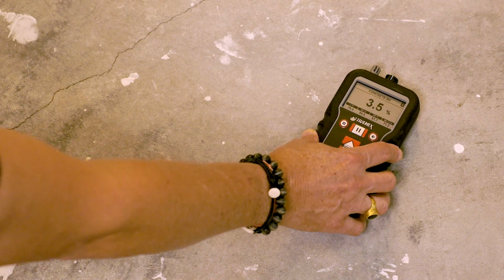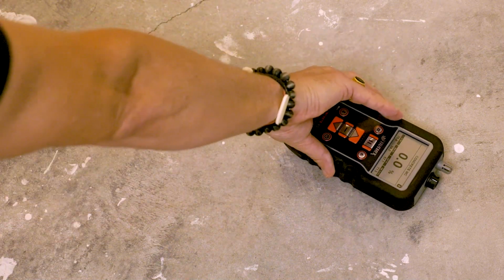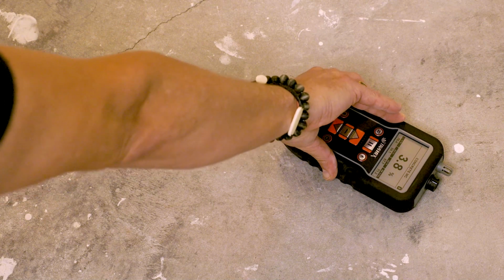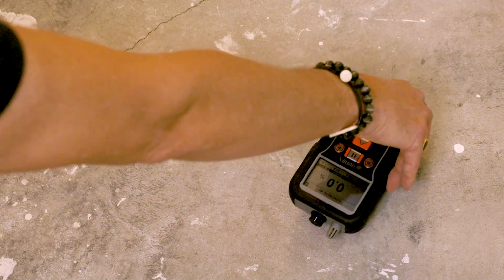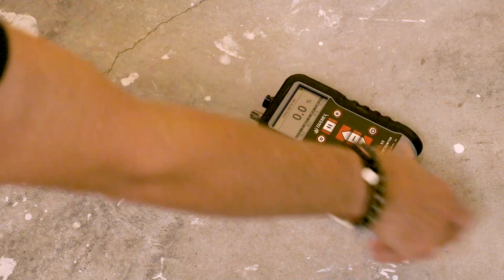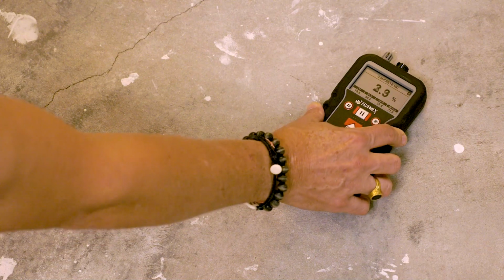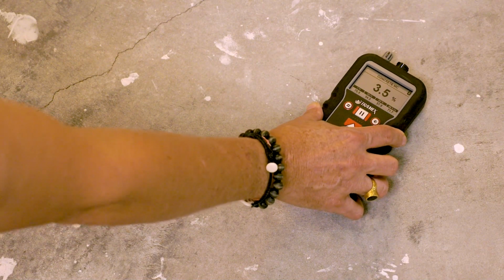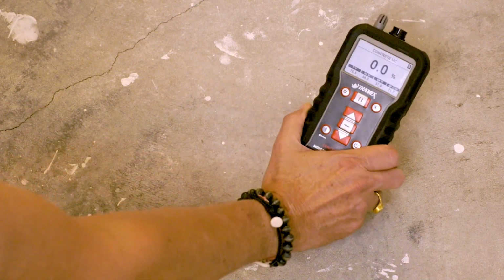And in each place we take a reading, we want to go around the horn, as we say. So we're going to do one at 12 o'clock. We're going to take another reading at 3 o'clock. We'll take another one at 6 o'clock, 9 o'clock, back to 12 o'clock. And then we're going to take the highest number. So my highest number was 4% in this area. So we'll note the 4% number.